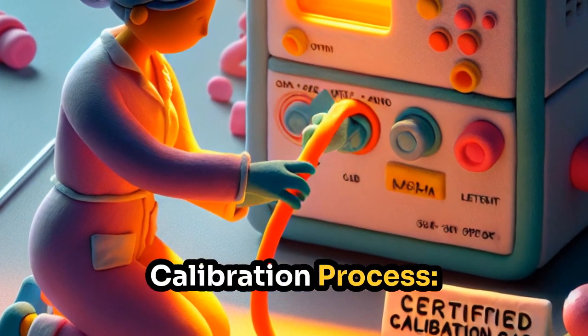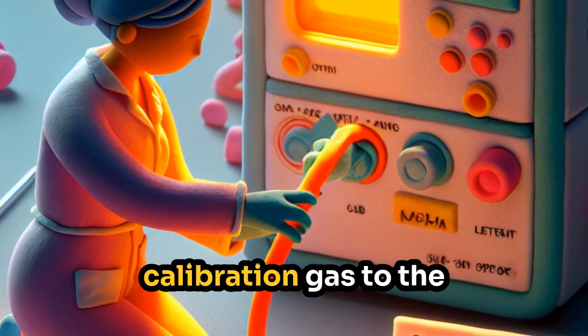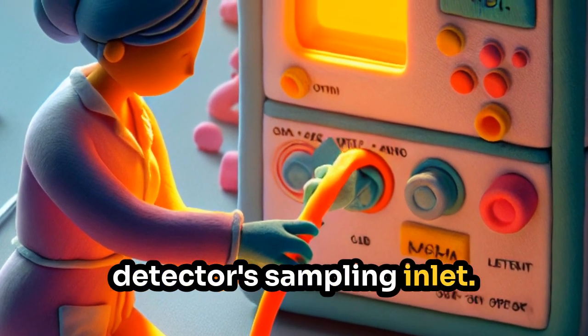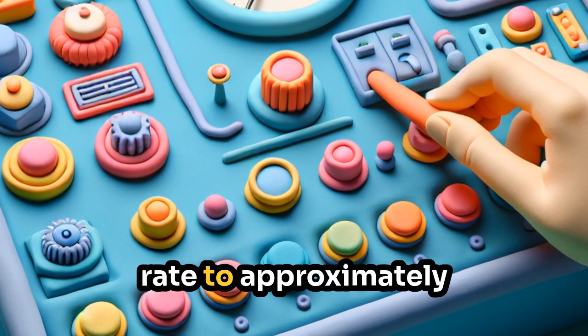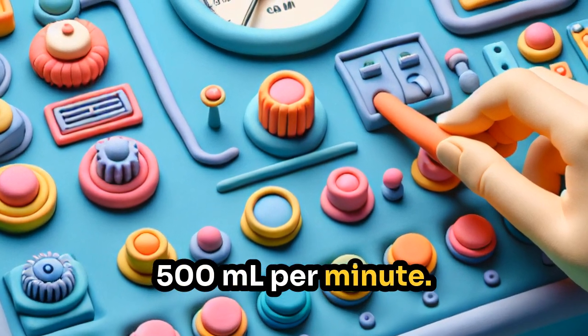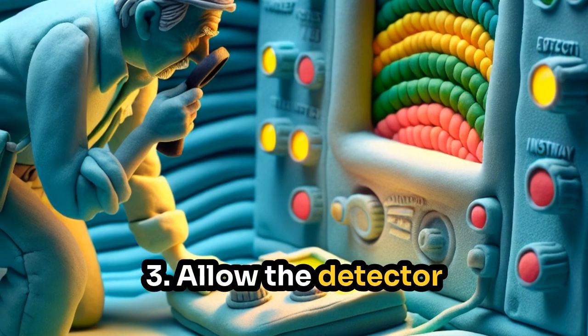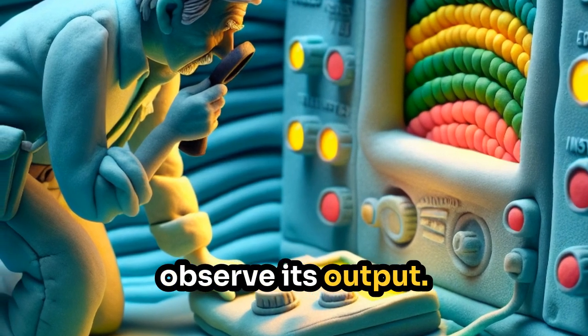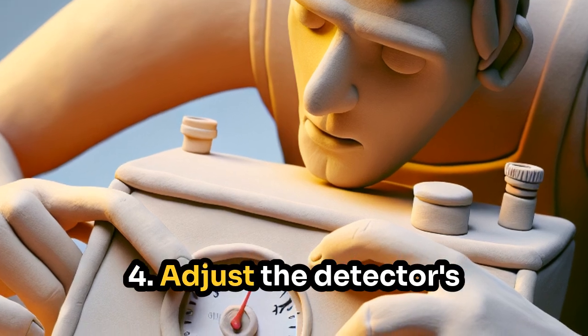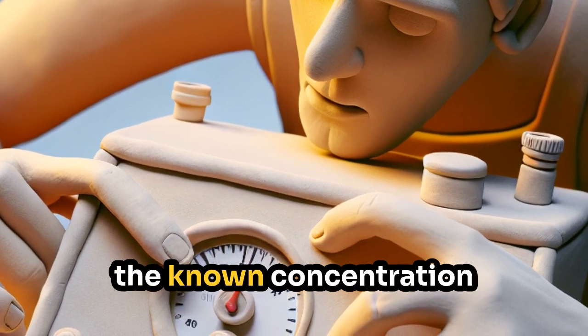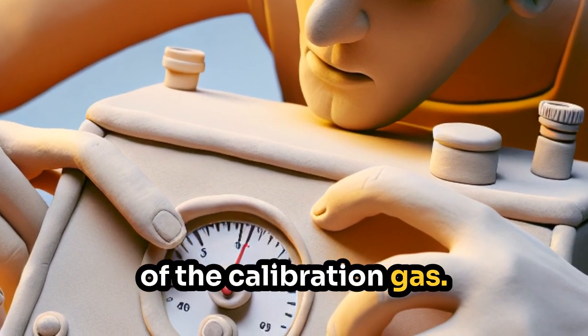Calibration process: 1. Connect the certified calibration gas to the detector's sampling inlet. 2. Set the gas flow rate to approximately 500 milliliters per minute. 3. Allow the detector to stabilize and observe its output. 4. Adjust the detector's response to align with the known concentration of the calibration gas.